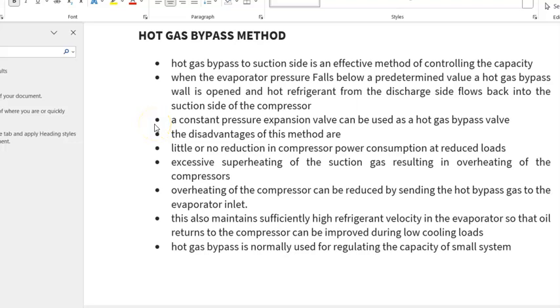So, the hot gas bypass method. Hot gas bypass to the suction side is an effective method of controlling the capacity. When the evaporator pressure falls below a predetermined value, a hot gas bypass valve is opened and hot refrigerant from the discharge side flows back into the suction side of the compressor.